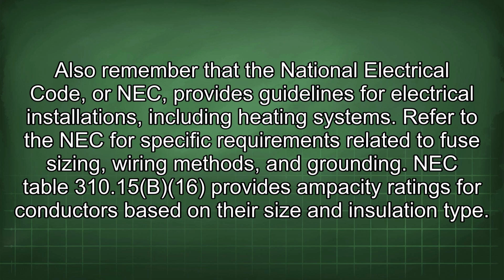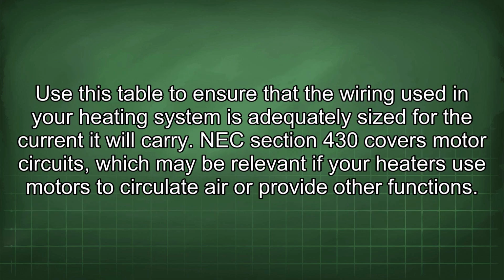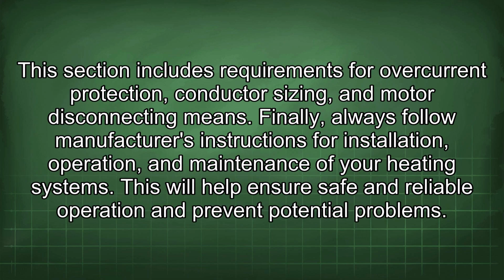NEC Table 310.15(B)(16) provides ampacity ratings for conductors based on their size and insulation type. Use this table to ensure that the wiring used in your heating system is adequately sized for the current it will carry. NEC Section 430 covers motor circuits, which may be relevant if your heaters use motors to circulate air or provide other functions. This section includes requirements for overcurrent protection, conductor sizing, and motor disconnecting means.